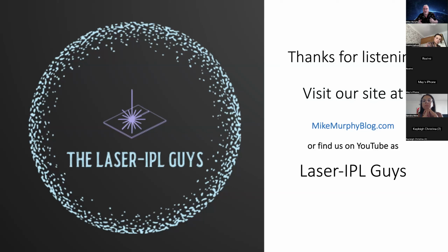What goes in is the maximum amount of power that's available. I don't want to get into the electronics of this. But if you've got a machine that says it's 2,000 watts coming out of the wall, that's powering the machine, then what comes out of the other end onto the skin can easily be less than 2,000. It can actually be more than that, depending on designs, more for pulse systems. But the two numbers are different. So when you see on the back of the machine that it says power, it can say something like 2,000 W, or sometimes they say 2,000 VA, which is another way of expressing power.